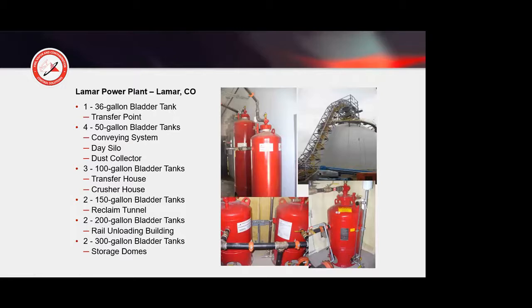Different systems, these are some Class A systems that have been put in place. This was for the protection of Class A combustible dust, in particular Powder River Basin coal. These are smaller systems because the sprinkler density in these conveyors or a dust collector or silos is usually 0.15 to 0.2 gallons per minute per square foot. The proportioning rate would be a 1%, and the duration is usually about a 10 to 15 minute duration of agent, usually with a 10 or 15 minute reserve.